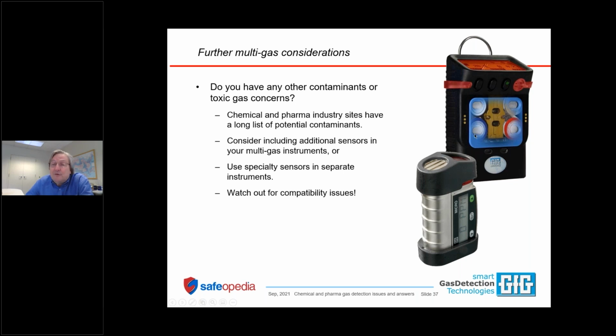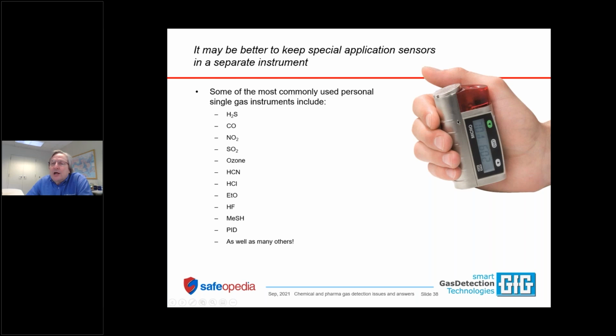Watch out for compatibility issues. There are some combinations of sensors that you don't want to have in the same multi-sensor instrument. For instance, nitrogen dioxide and sulfur dioxide. Exposing an SO2 sensor to nitrogen dioxide drives the reading really deeply negative. You'll have a downscale negative alarm. And the opposite is true as well. Each gas drives the other respective sensor deeply negative. So a lot of times it just makes more sense to keep the odd gas out in a separate instrument.